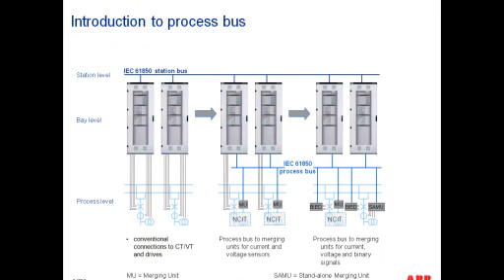So now we take a look at the control house layout from a process bus perspective. What we find here is that at the process level, we have our current and voltage transformers. And this would be essentially a conventional design, where from my current and voltage transformers I have copper wires that go into my panel inside my control house. And the relays essentially operate based on those signals. There's also copper wiring that goes from the relays onto the switchyard to operate the breaker.